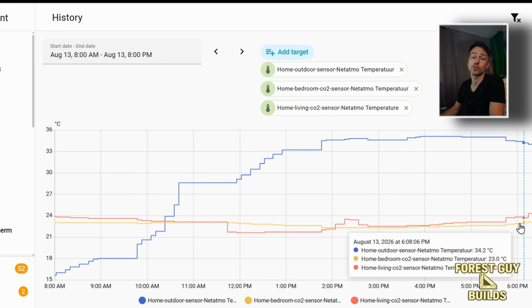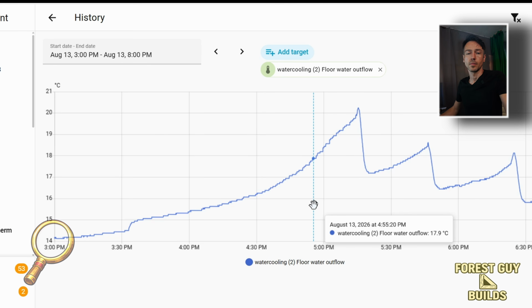So I think that's a really nice outcome of this experiment so far. It's also quite relevant, because I'm sending water to the floor at a pretty low temperature of around 14 degrees. Looking at a lot of information online, that's definitely lower than would normally be recommended, mainly because of the risk of condensation on the floor. But running the system like this over the last few days, I haven't had any condensation issues, simply because the actual surface of the floor never reached a temperature low enough to cause it.